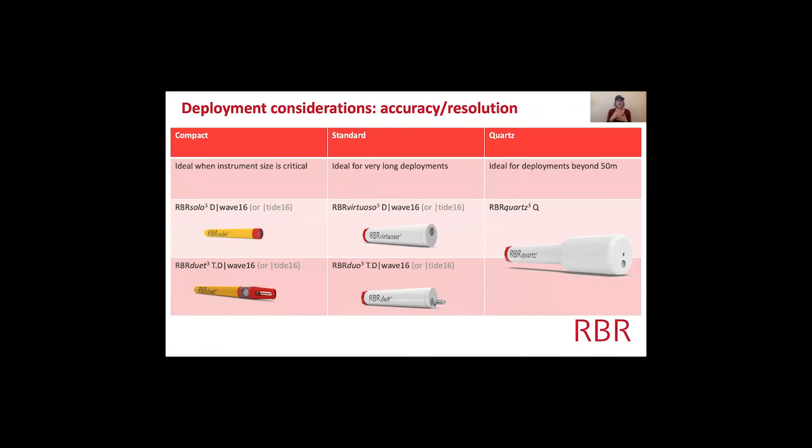Now I'm going to talk about the different instruments at RBR and why you'd pick one over another — this comes down to accuracy and resolution. Compact loggers are ideal when instrument size is critical. For example, a colleague actually buries instruments, and it's much easier to dig a hole for a small Solo-T than a larger Virtuoso. You can get a Solo-D Wave 16 or a Duet-TD Wave 16 — the Duet adds a thermistor to also measure temperature.